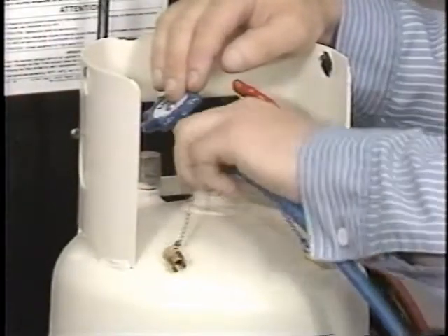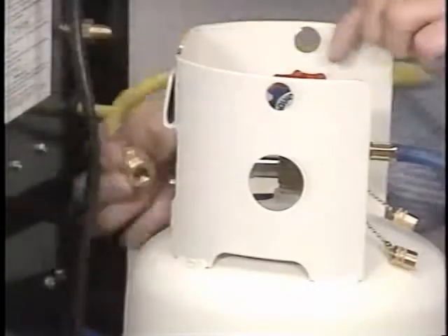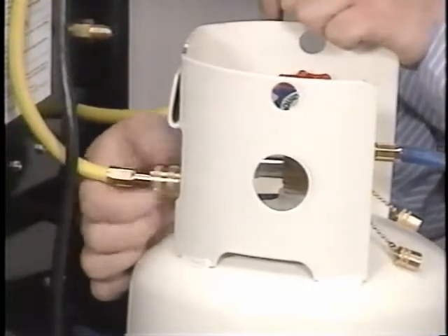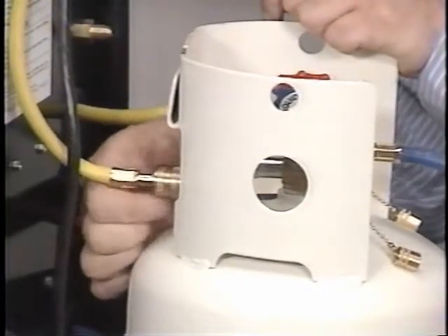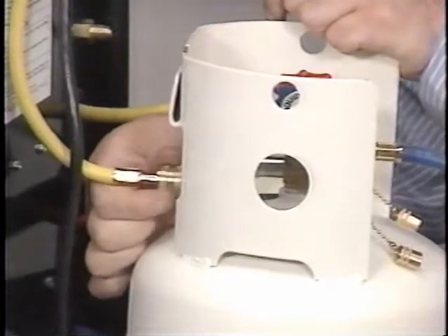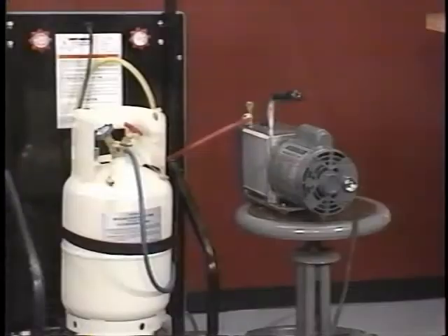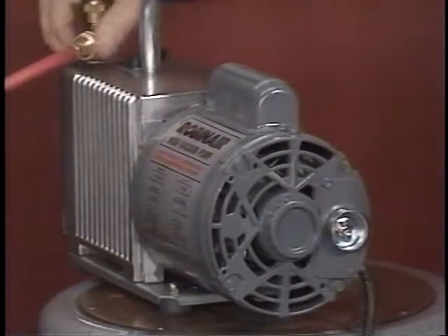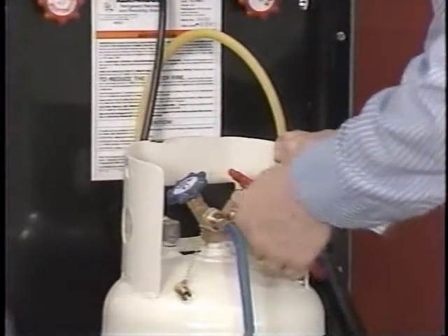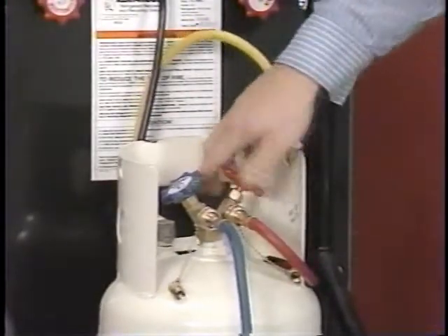Attach the blue hose to the liquid port and the yellow hose to the elbow on the tank. This hose is part of the air purge system that bleeds air from the tank. Attach the red hose to a vacuum pump. Run the vacuum pump for 10 minutes to evacuate moisture and air from the system. Switch off the pump. Disconnect the red hose and attach it to the gas port on the tank. Open the gas valve. The system is ready to recover R12.